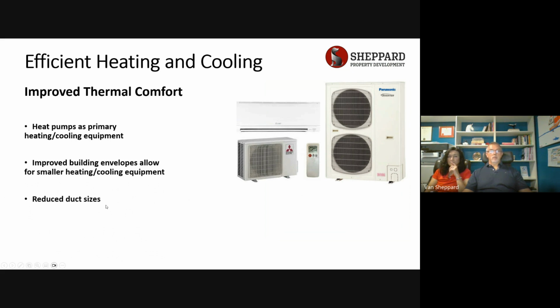The reduction in heat requirements also reduces your duct sizes, and that makes installation easier. It's easier to run a main duct that's 6 inches in diameter than to run an 8-inch by 30-inch duct through your building. So it makes life a lot easier there. Something else, when your envelope is really tight and you're losing a lot less heat through your windows and your walls, you don't need to run your heat supplies in your rooms out to the exterior. So that lets you design a simpler system with less ductwork and provide your heat from the warm side of the room, and it's still going to keep the room comfortable. And that also, less ductwork, fewer duct runs, and reduced duct sizes makes your system install easier and makes it easier to get a better building.